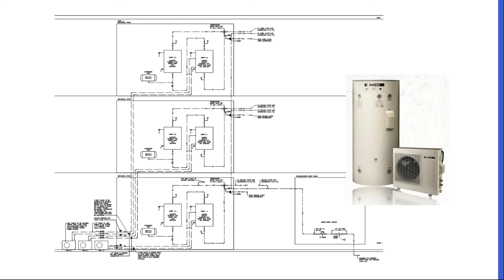Can you describe why the Sanden shut down when it got so cold? If you want more on it, contact John Miles, their technical representative who's been deeply involved with this. It was some kind of system failure -- it should have converted to a defensive mode where it keeps circulating through the unit, but somehow the unit instead shut down, stopped recirculating, and of course it froze solid at this kind of temperature. We think part of the problem was that we put the outside unit in a semi-protected, semi-enclosed space with vent holes, and it actually got colder in that space than the outside temperature because the Sanden is producing cold and it's outside cold.